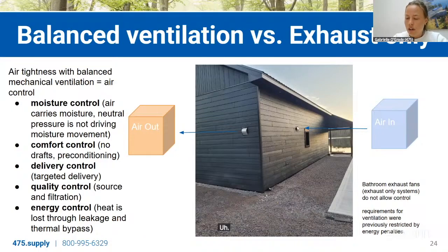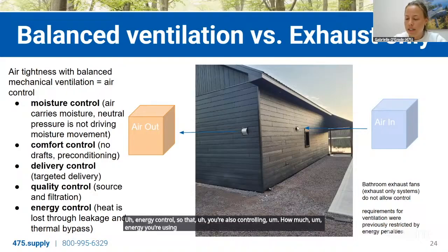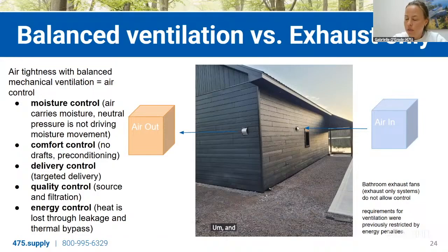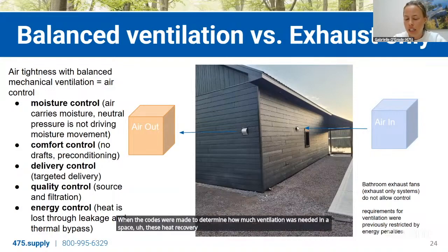Energy control, so that you're also controlling how much energy you're using because you're eliminating leakage, the heat that's lost through leakage in your envelope and thermal bypass. Also, one thing to consider is that when the codes were made to determine how much ventilation was needed in a space, these heat recovery and enthalpy recovery ventilation systems were not yet available.